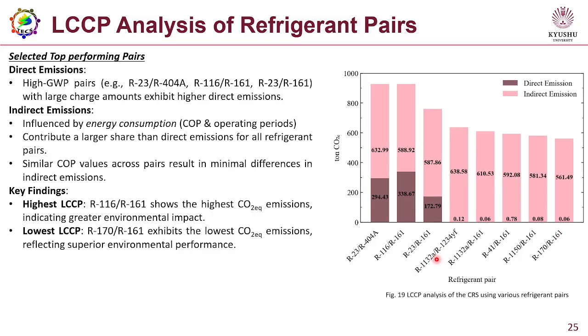And when we switch from R23 and 404A to R170 161, we have almost 40% reduction in the CO2 emission.